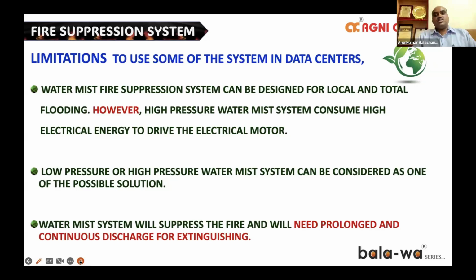Water mist fire suppression can be designed for both local as well as total flooding. But the important limitation of a water mist system in a data center is that they consume very high electrical energy to drive the electrical motors. And also, water mist will suppress the fire. But in order to extinguish the fire, we will need a more prolonged and continuous discharge. Which means, as I said earlier, the water mist system will bring down the temperature to less than 100 degrees centigrade. But to completely extinguish the fire, it will need a prolonged and continuous discharge.